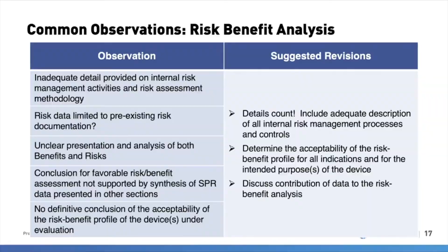And there should be a point-by-point presentation and discussion of the contribution of all available clinical data to the overall risk-benefit analysis. This is why I said that this is a very large section, and because it's where everything comes together. I repeated that for a reason. It's a dense sentence. Determine the acceptability of the risk-benefit profile for all indications and for all intended purposes. Stating has been on the market for X number of years is not an acceptable justification. And finally, as I said, clearly include a definitive conclusion statement of the acceptability of the risk-benefit profile of the device under evaluation.